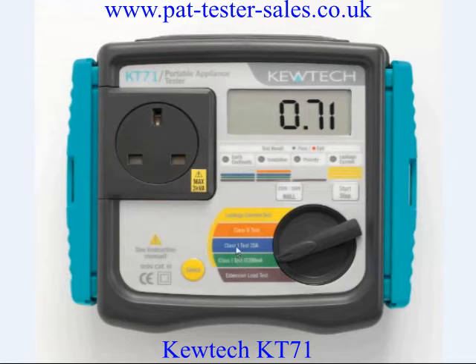The class 1 will do a standard class 1 test at 20 amps for the earth test and a 500 volt insulation test. The class 2 will skip the earth and only carry out a 500 volt insulation test.